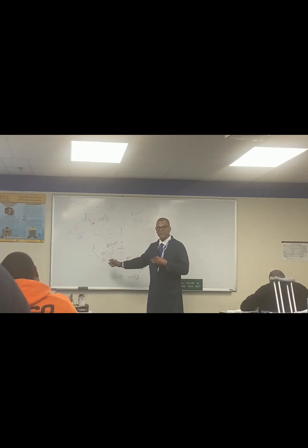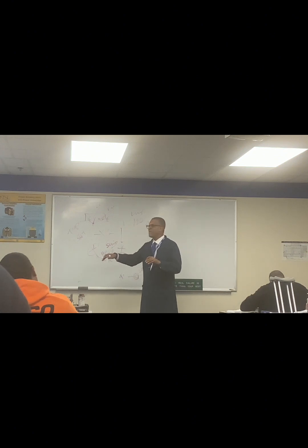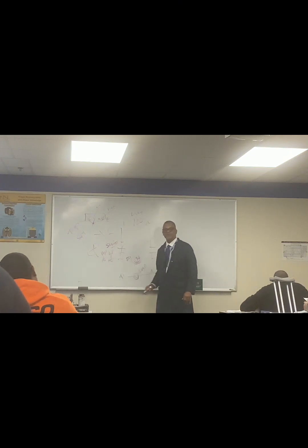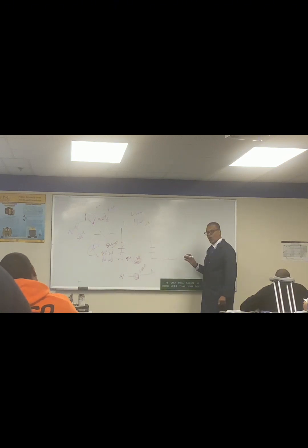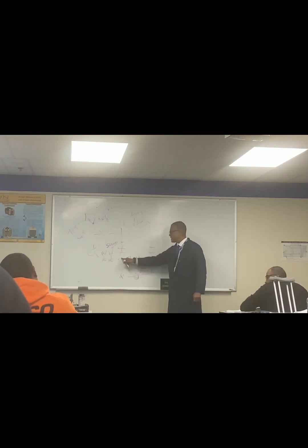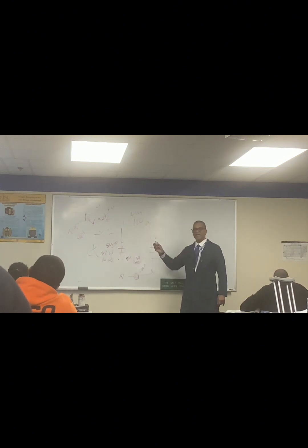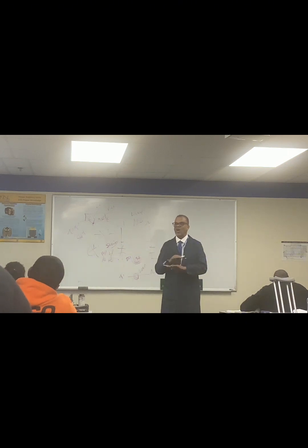senses a failure. Low pressure, low temp, low refrigerant. High pressure, dirty condenser. High pressure, outdoor fan failed, there's no airflow, high temperature, and the high pressure switch opens. The purpose of the high or low pressure switch opening is to open the contactor. If we open the contactor, the compressor and outdoor unit are off. So we're not operating it in an unsafe environment for the machine.